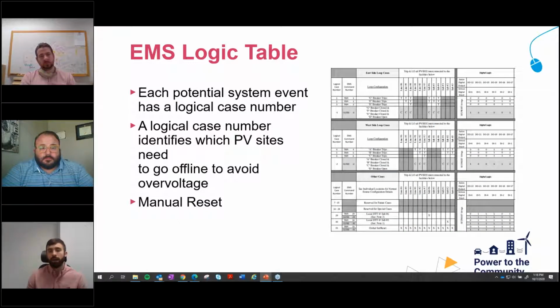The first part of this solution really had to happen in our EMS system. As Kevin said, overvoltage is an issue, and it's something we need to be aware of when contingencies happen. Breakers open, we lose transmission lines or whatnot. So we worked with our protection and transmission planning group to identify which breakers opening or line loss would result in these overvoltages and which corresponding PV sites need to trip off to maintain reliability and voltage stability. You can't really see it here, but in the logic table there are a bunch of different case numbers assigned, and each correlates to a specific breaker or transmission line issue, and then identifies which PVs need to trip. That is then translated to a 6-bit command that goes out when there's an issue.